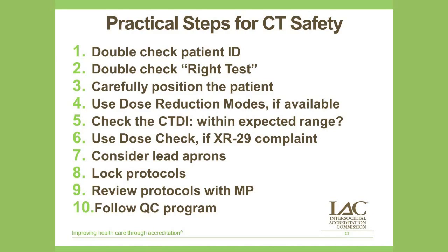Make sure you've got lead aprons available for use. Lock down your protocols. If they're variable, lock them down. Most cone beams are locked in. A multi-detector CT is not so much, but you can password protect them so that technologists cannot change them. Review protocols with your medical physicist and follow your QC program. Every machine has a recommended QC program. You should follow it religiously, and it will be required for IAC accreditation as well.